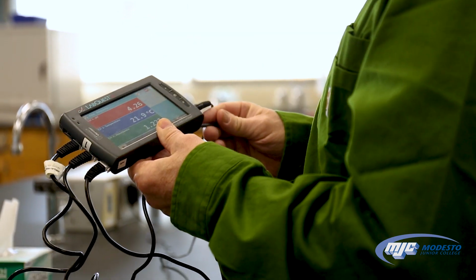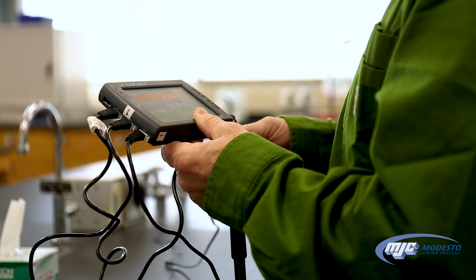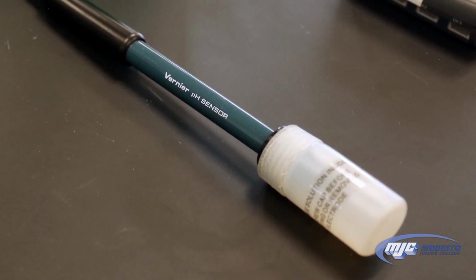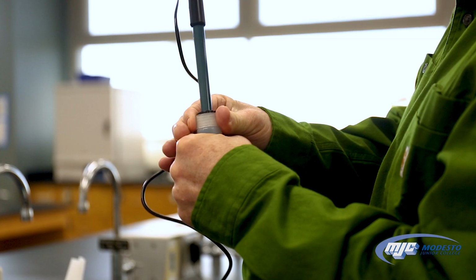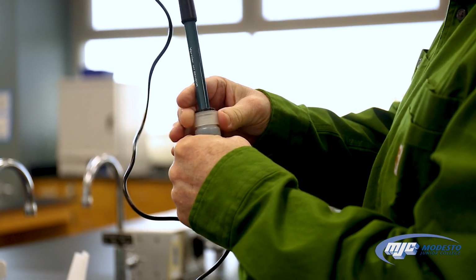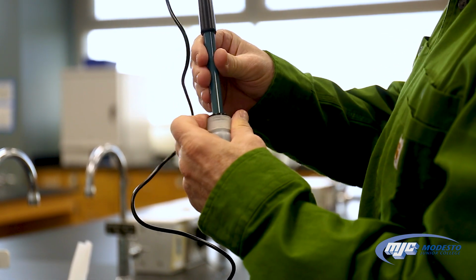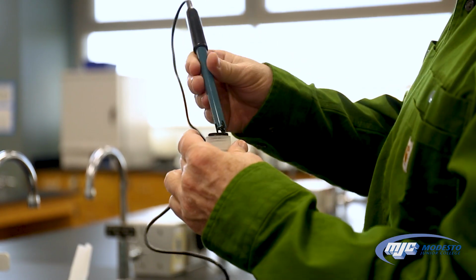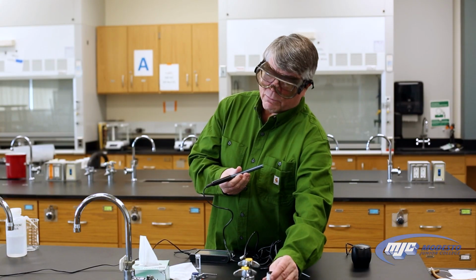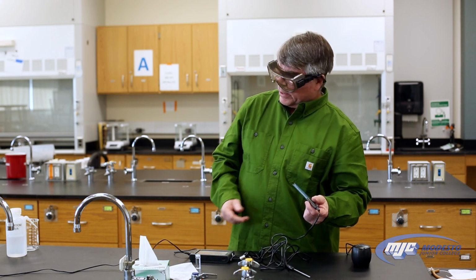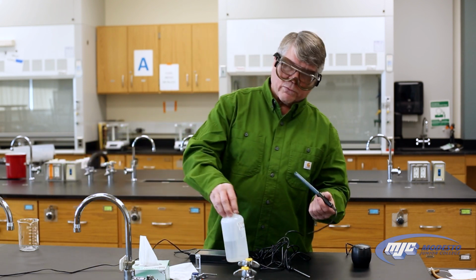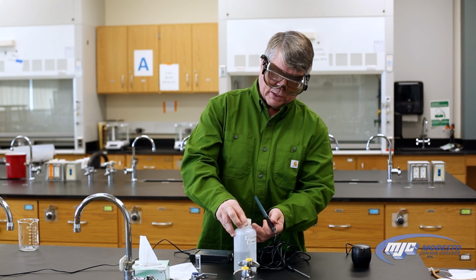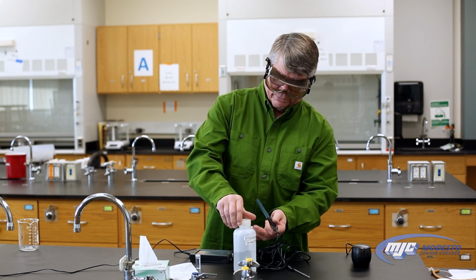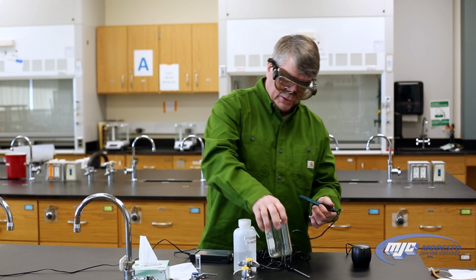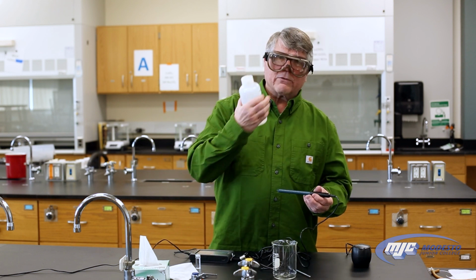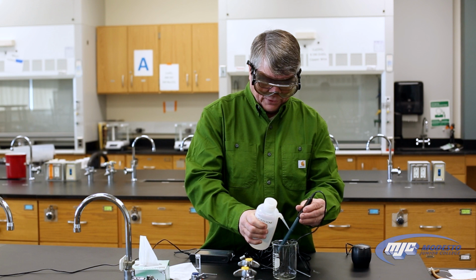All right. Now with the pH probe, guys, to use it, you take it out of the storage solution by loosening this cap right here. You don't have to take it all the way off. When it's loose enough, the pH probe itself will come out. And set this aside somewhere where hopefully it doesn't spill. I tend to spill them a lot. Now, what you're going to want to do before you measure the pH of any solution with the pH probe is clean it off. So take a waste beaker, some deionized water, and rinse off the outside of the probe into the waste beaker.